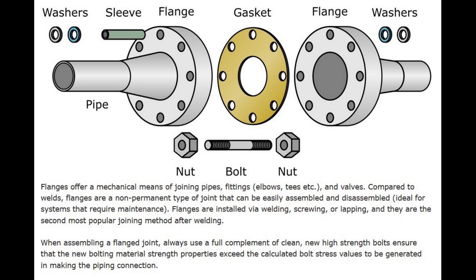When assembling a flange joint, always use a full complement of clean, new high-strength bolts. Ensure that the new bolting material strength properties exceed the calculated bolt stress values to be generated in making the piping connection.